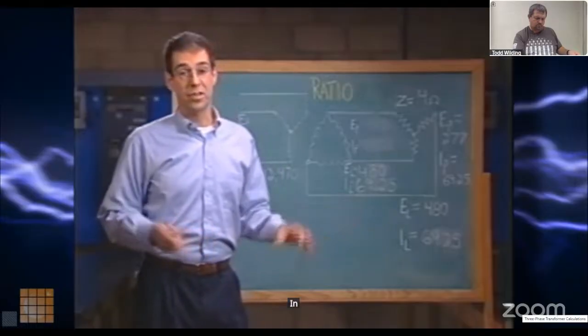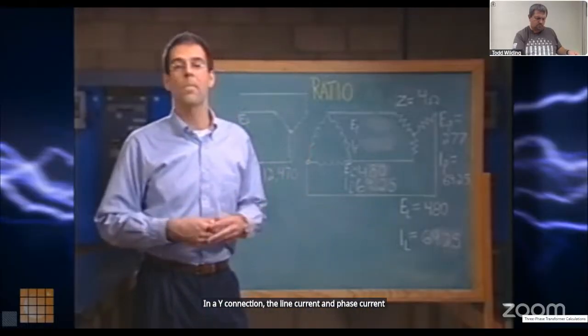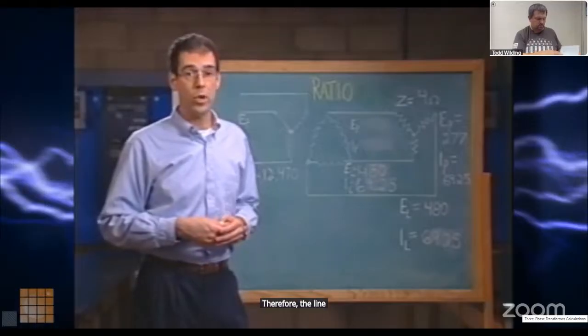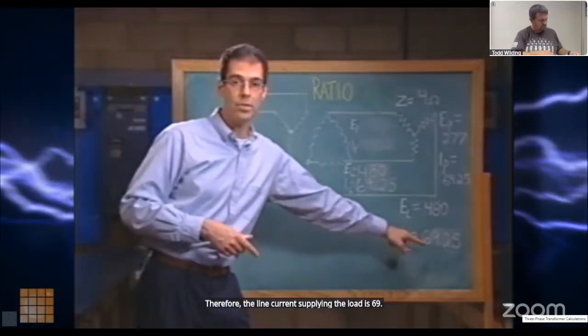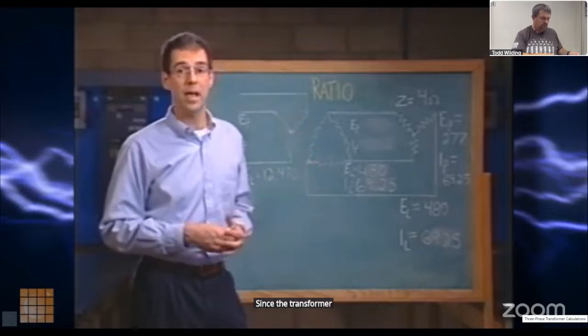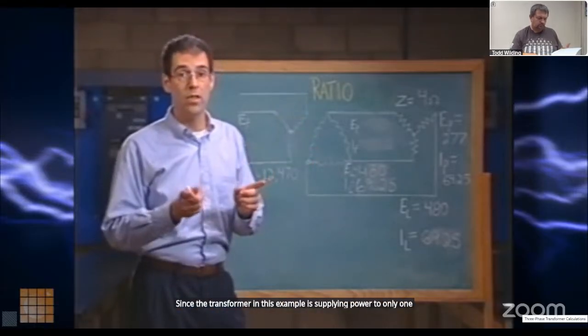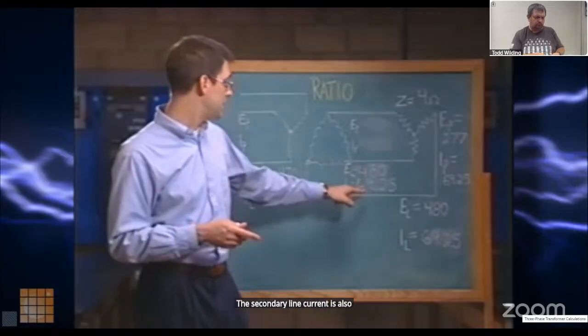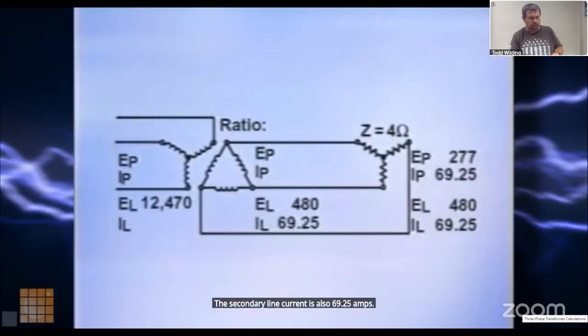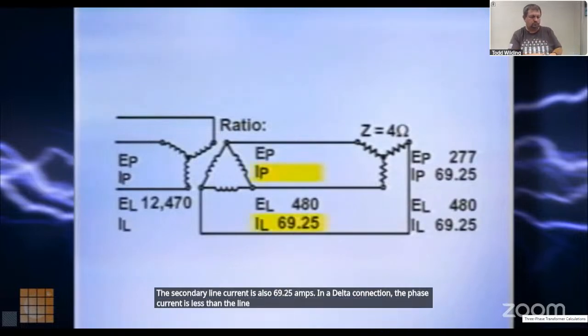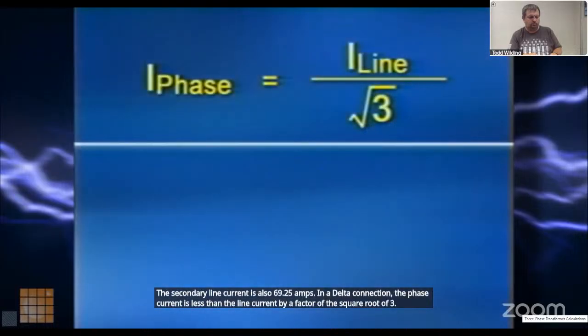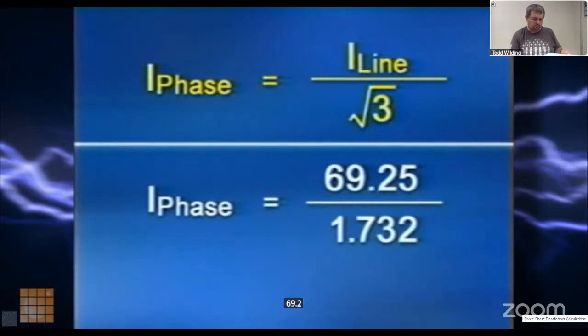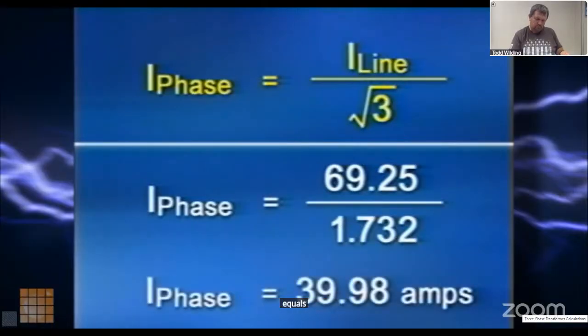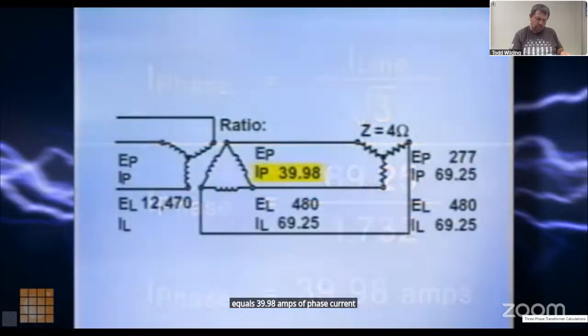In a Y connection, the line current and phase current are equal. Therefore, the line current supplying the load is 69.25 amps. Since the transformer in this example is supplying power to only one load, the secondary line current is also 69.25 amps. In a delta connection, the phase current is less than the line current by a factor of the square root of 3. 69.25 amps divided by 1.732 equals 39.98 amps of phase current in the transformer secondary.